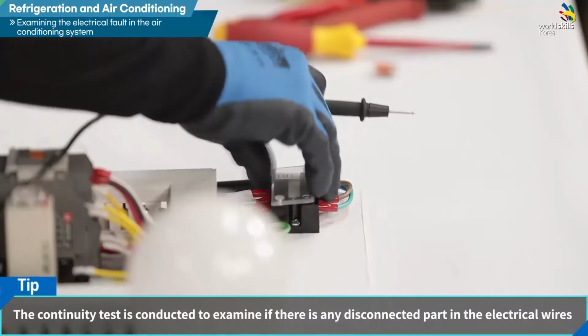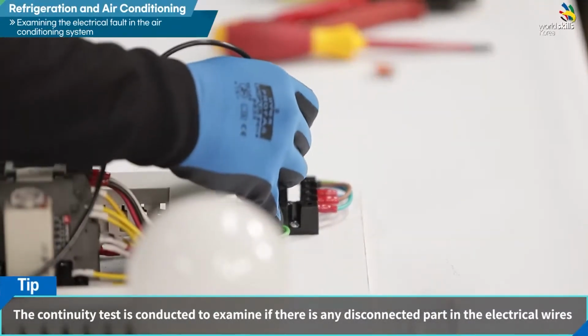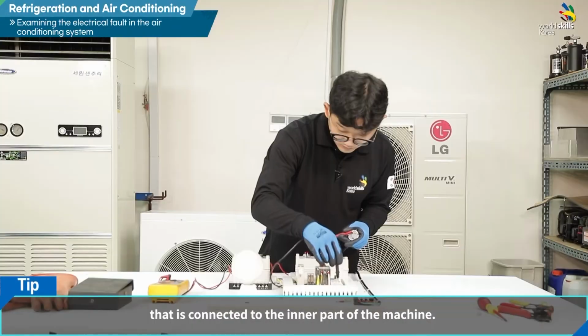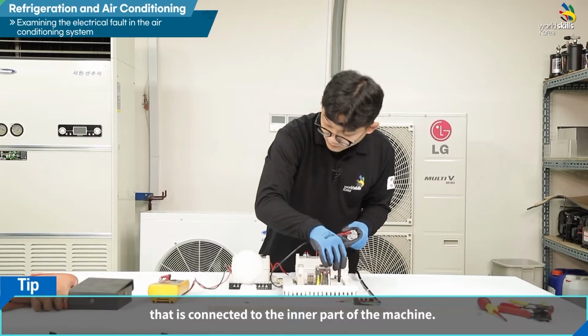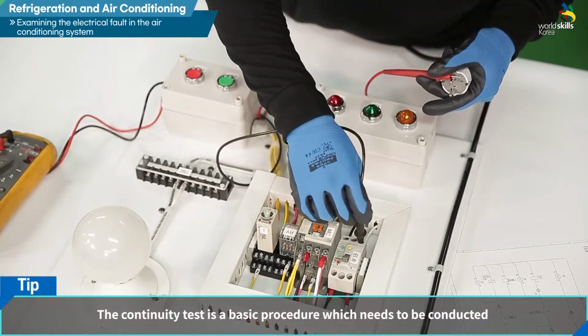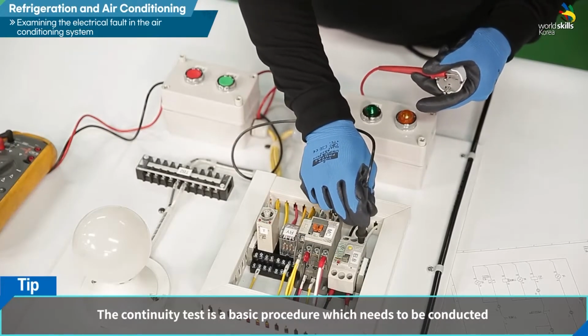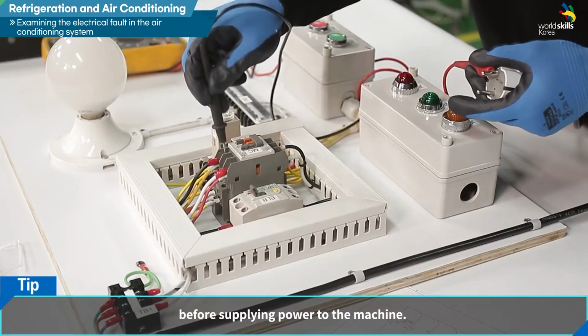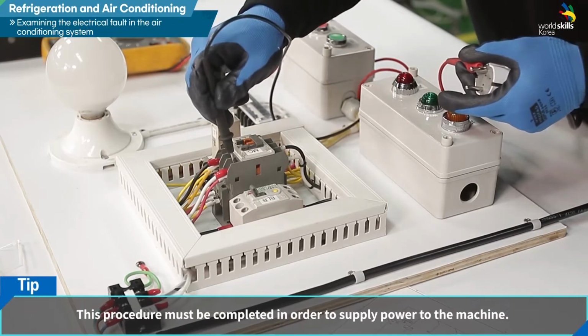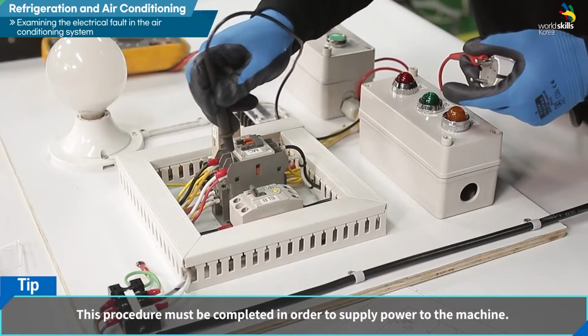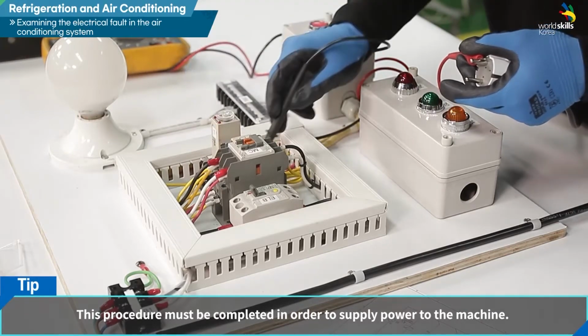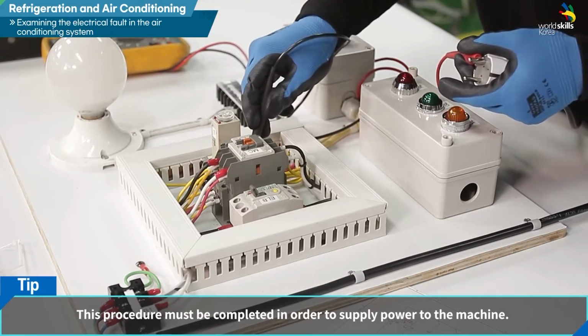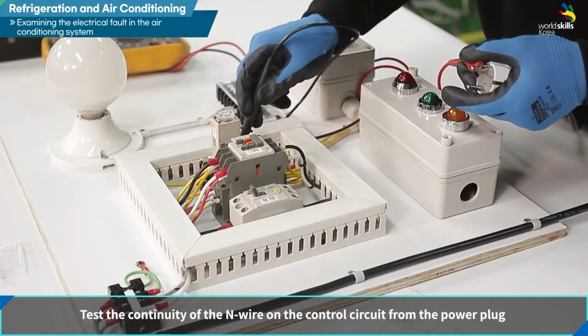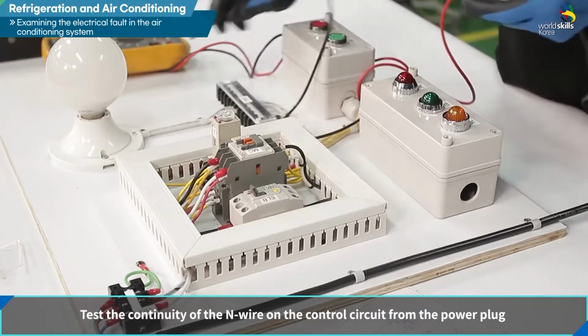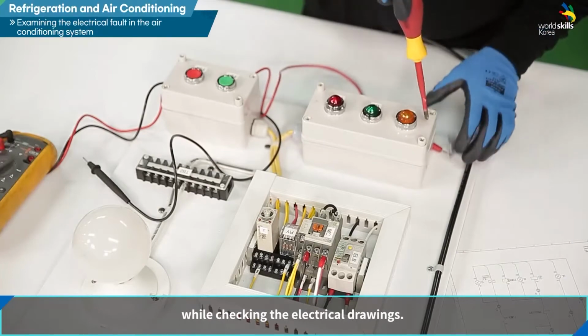The continuity test is conducted to examine if there is any disconnected part in the electrical wires that is connected to the inner part of the machine. The continuity test is a basic procedure which needs to be conducted before supplying power to the machine. This procedure must be completed in order to supply power to the machine. Test the continuity of the N wire on the control circuit from the power plug while checking the electrical drawings.